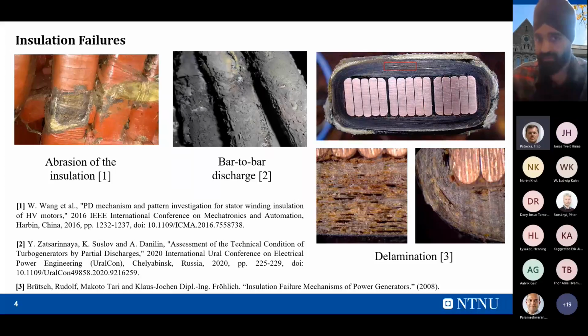So I'll explain this. These are the 15 copper strips, and around them we have an insulation of epoxy and mica. Now, during frequent start and stop operation, the temperature of this insulation and the copper strips changes from 40 degrees Celsius, or ambient temperature, to the upper limit of that particular insulation class. It's near about 110 degrees Celsius to 130 degrees Celsius. It depends upon the class of insulation we are using.